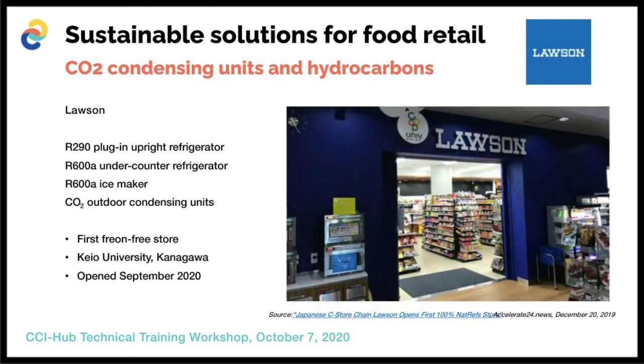This year, my apologies, they have installed the first full natural refrigerant store. To explain, they combine their showcases powered by CO2 condensing unit with hydrocarbons that are being used in the kitchen, the back end of the store, when the different dishes are being prepared. So there are commercial refrigerators and ice makers, and in this pilot store, they have installed all the systems using hydrocarbons, R290 and R600A. So this is 100% refrigeration with natural refrigerants, first of its kind in Japan.